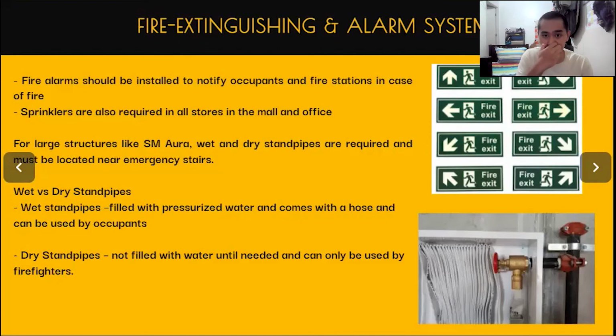So what's the difference between wet and dry standpipes? Wet standpipes, as the name says, are filled with pressurized water. It's wet and comes with a hose that can be used by occupants. The hose is there with the required length so that common occupants like us can also use the water coming out from it.